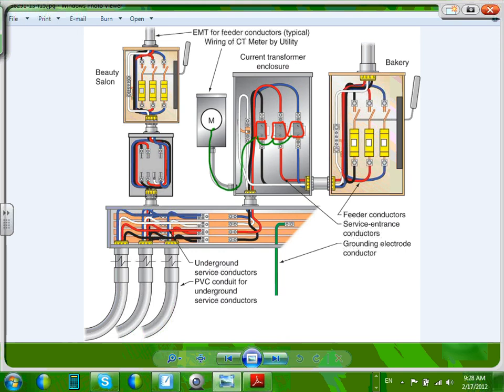So they sense, and they are most likely these ones, 400 amp to 5 amp. They call them 400 to 5. So every time it sees a 400 amp coming into the building, it will be seen as 5. Now you do proportional. If it sees 100 amp, it will see less. You do the proportion for the amps. Can you guys see how they tab them with these lugs? They land them in here and tab them directly with the lugs.